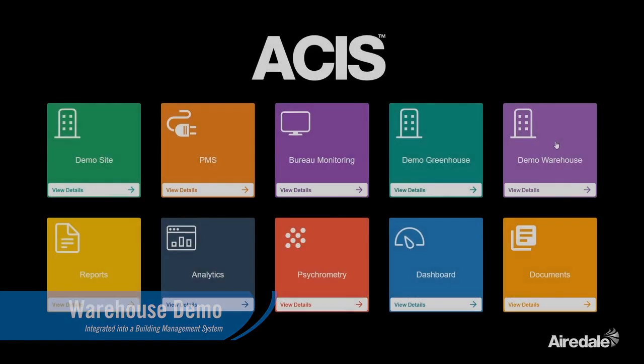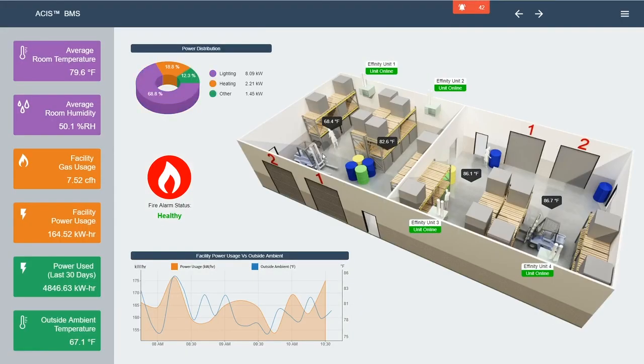And sometimes in loading bays, you may have a door that's been left open, and if it's very cold outside, you have the issue where you could be freezing water pipes and things like that. Obviously with this, you can have the temperature coming back from the space instantaneously. You can set alarms on your BMS, which means you can say, okay, if it gets below this temperature, generate an alarm, or if the unit fails or has an issue itself, you'll instantly know that it has that fault, and you can go and fix it before it becomes a problem in the building.